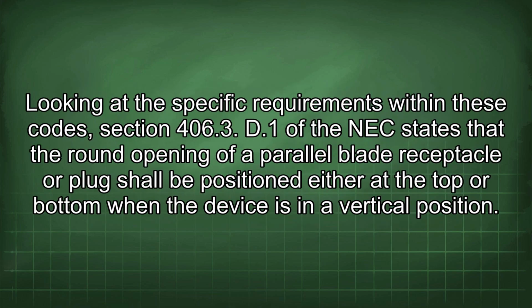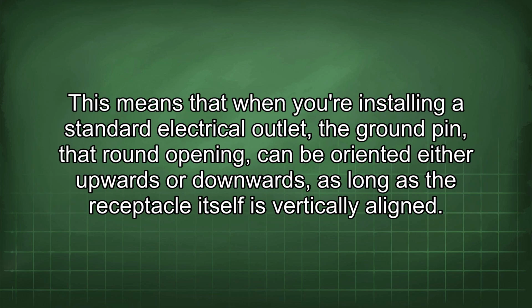Looking at the specific requirements within these codes, Section 406.3.D.1 of the NEC states that the round opening of a parallel blade receptacle or plug shall be positioned either at the top or bottom when the device is in a vertical position. This means that when you're installing a standard electrical outlet, the ground pin, the round opening, can be oriented either upwards or downwards as long as the receptacle itself is vertically aligned.